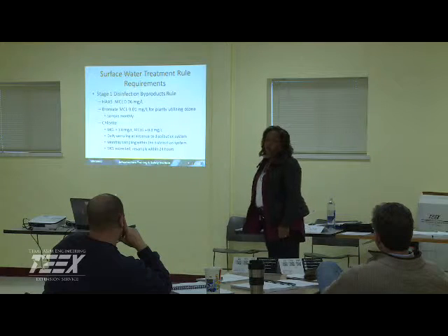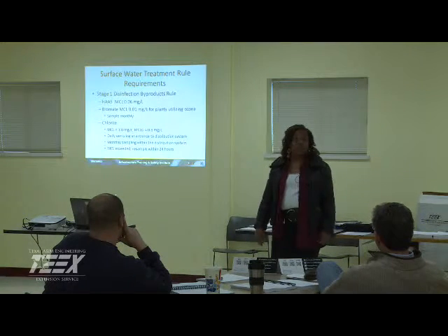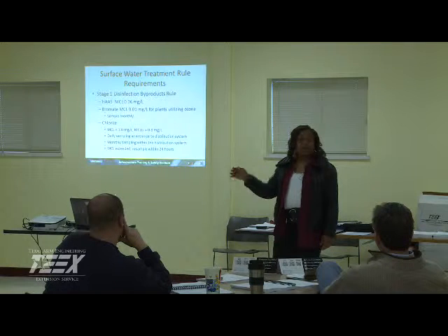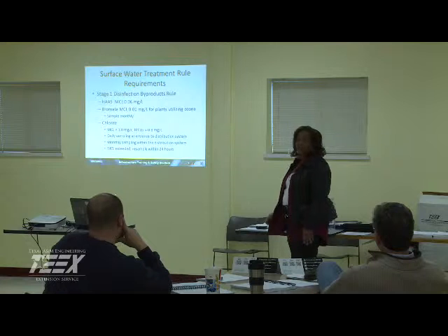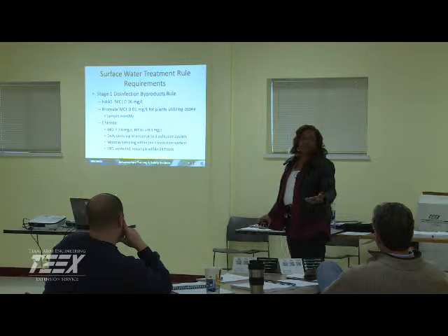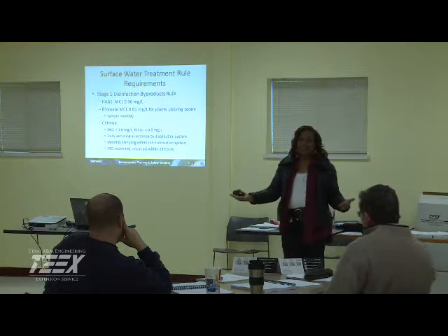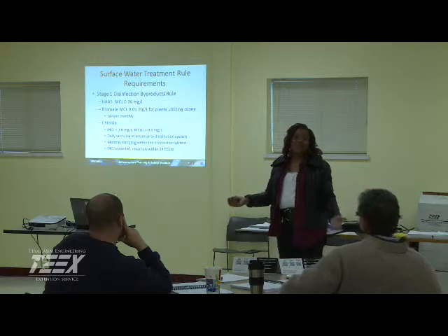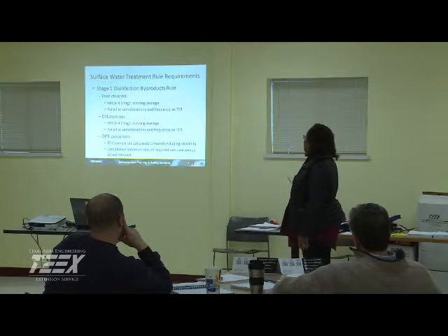Chlorite is formed when you are using chlorine dioxide as an alternative disinfectant. The byproducts, chlorite and chlorate, are also considered health issues for us. But it's an alternative because you don't have the production of trihalomethanes and haloacetic acids, six in one hand, half a dozen in the other. There's still a maximum level of this that you can have in the system.